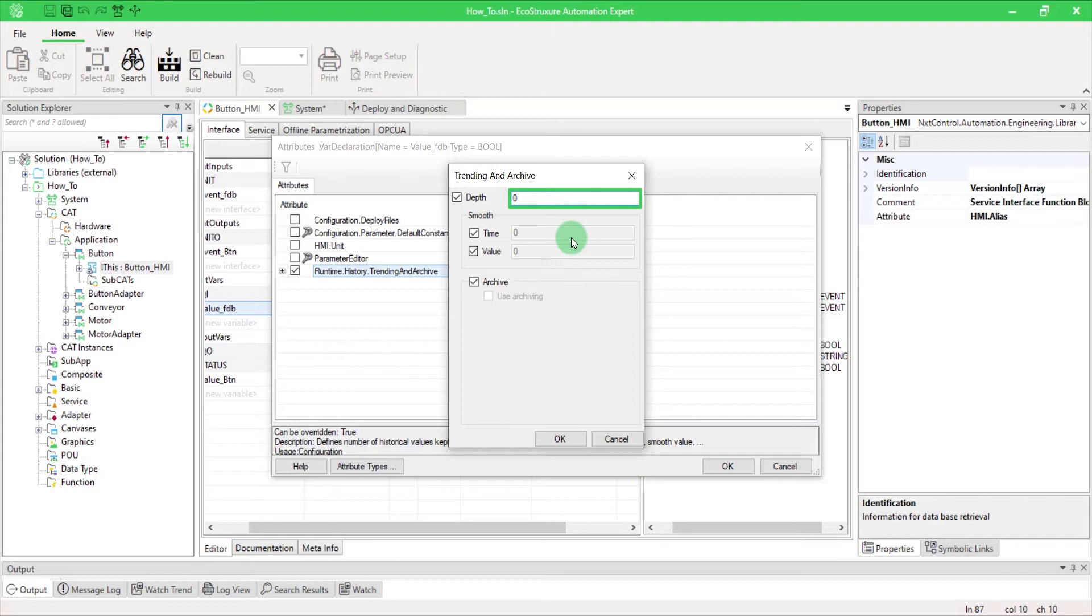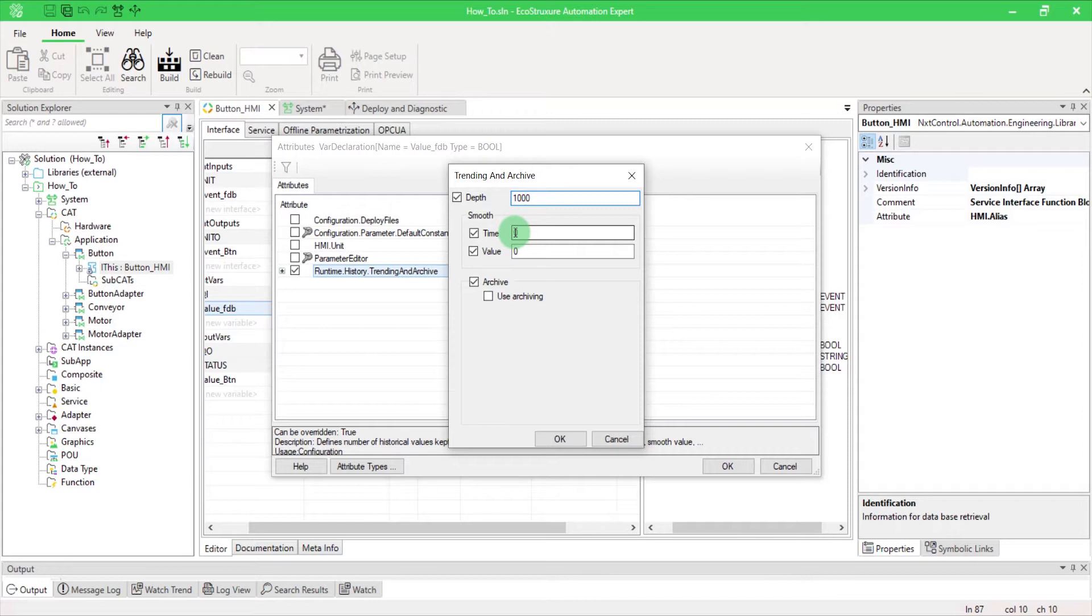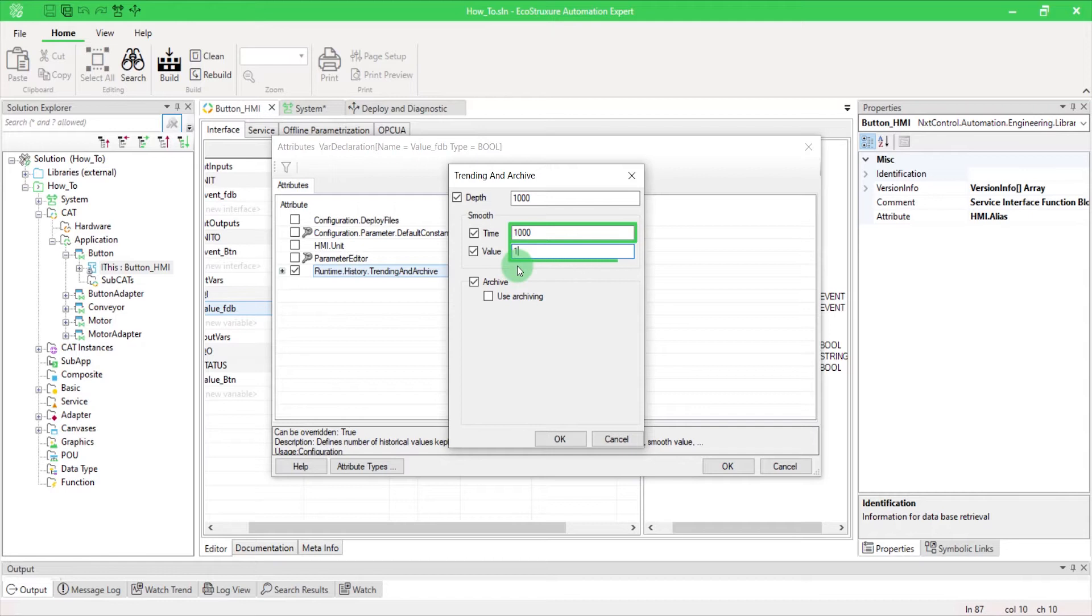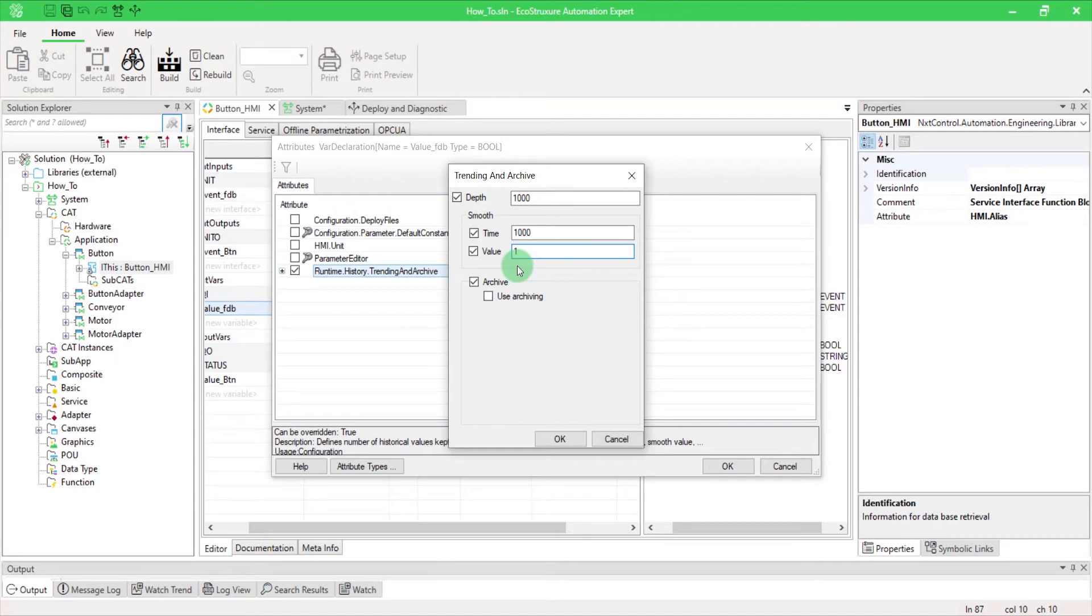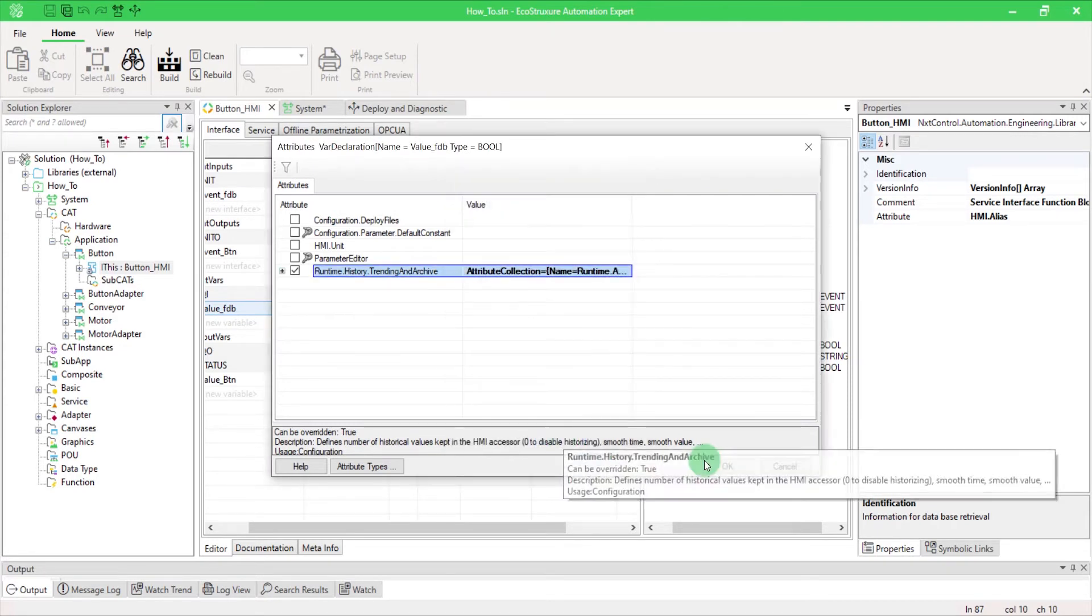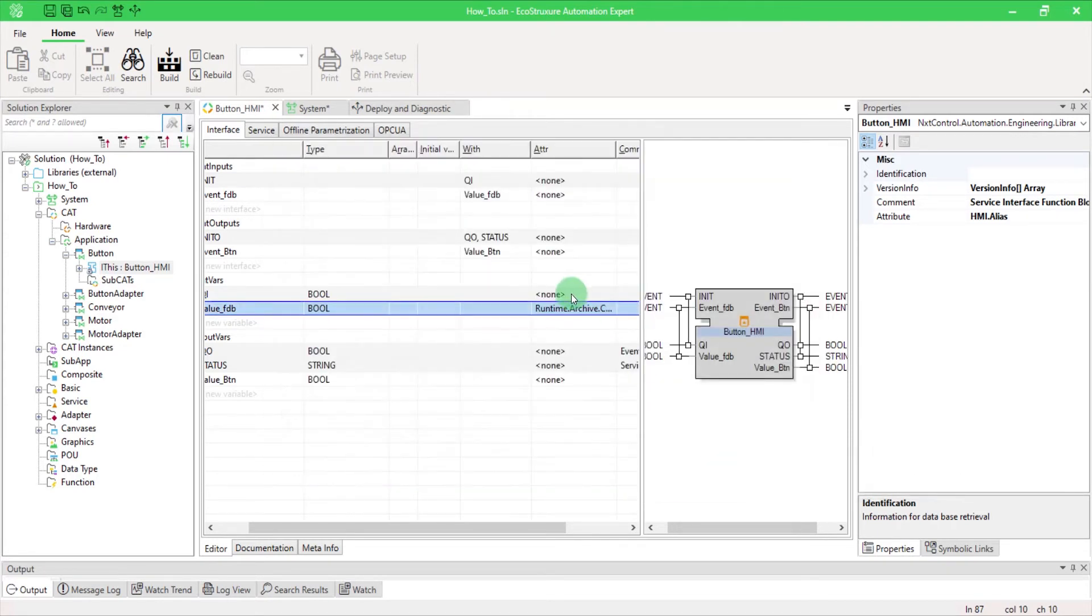Enter the maximum number of values to be archived. This is actually the circular buffer size. Enter the minimum wait time for the next value to be archived and the minimum difference between the previously archived value. Don't forget to select the Archive checkbox to make archiving possible and the Use Archiving checkbox to indicate that this variable must be archived.